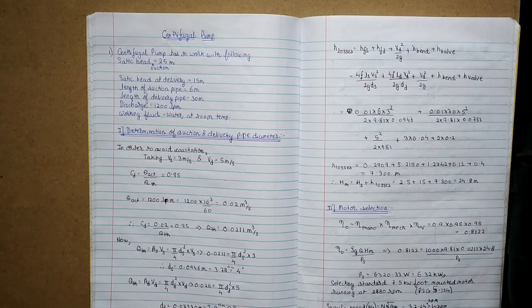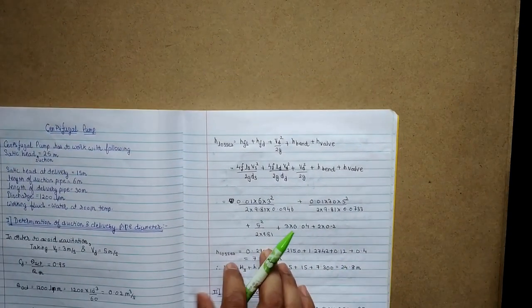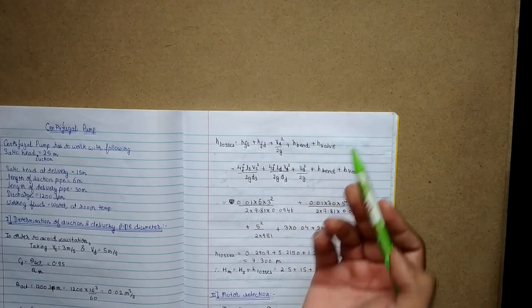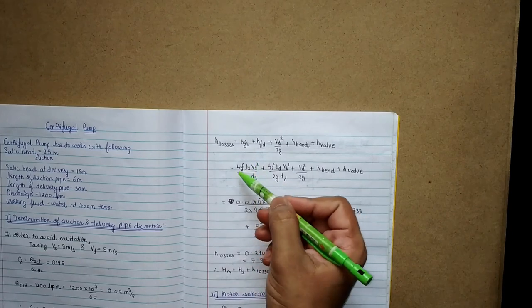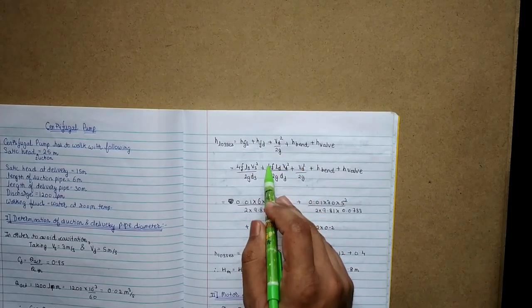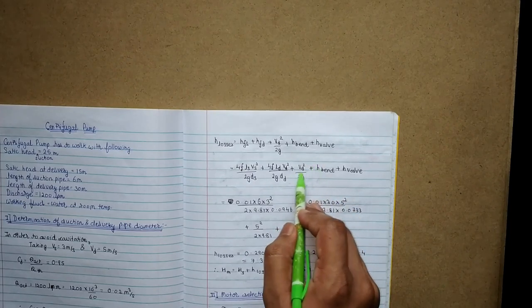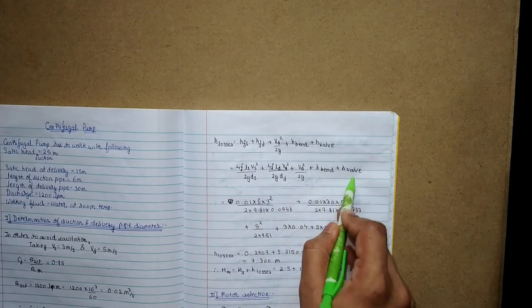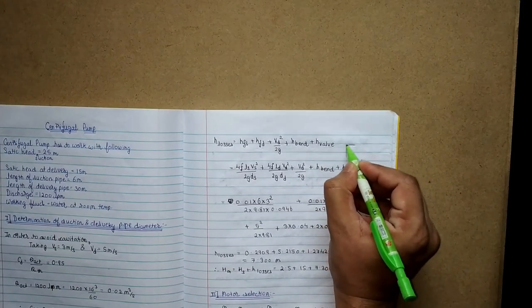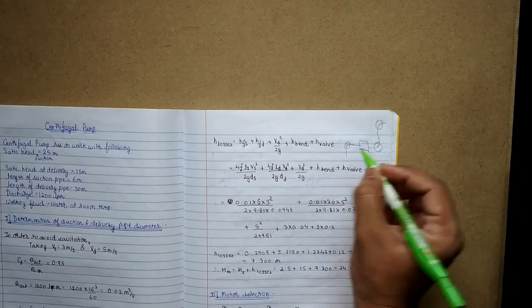After that we calculate the head losses. The formula is h_fs + h_fd + V_d²/(2g) + h_bend + h_valve. For h_fs we use the formula 4fL_s·V_s²/(2g·D_s), and for h_fd we use 4fL_d·V_d²/(2g·D_d) plus V_d²/(2g). The h_bend is the loss due to bends — we consider three bends: one at suction, one at the pump, and one at delivery.